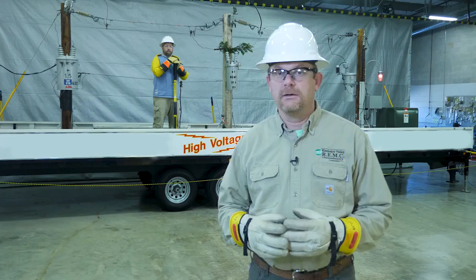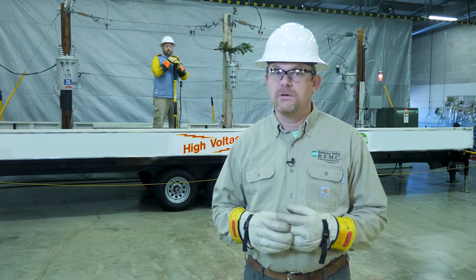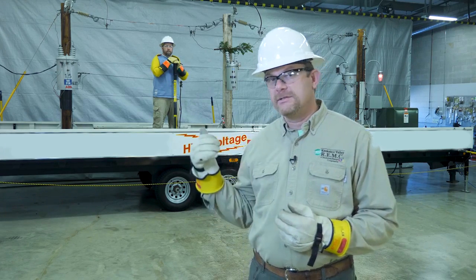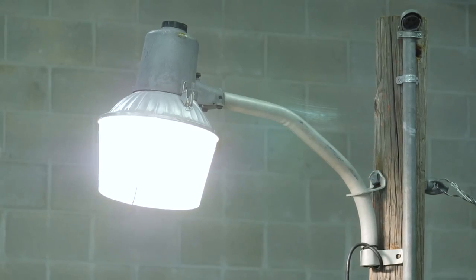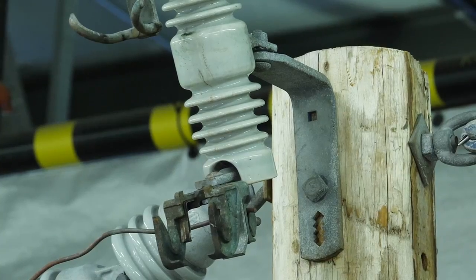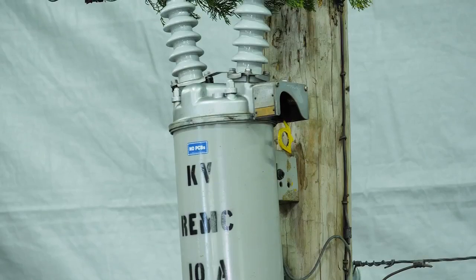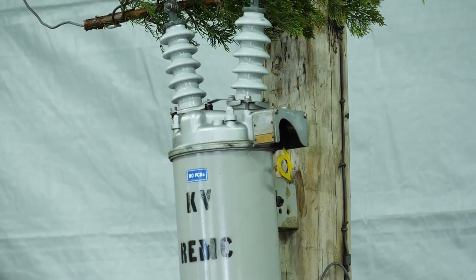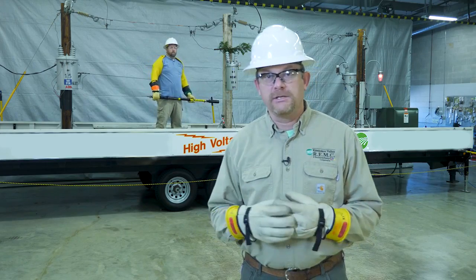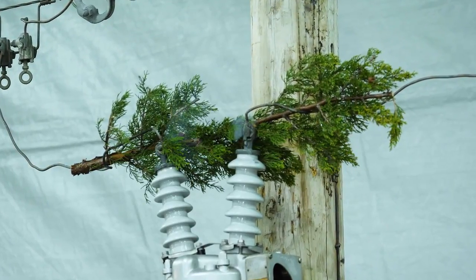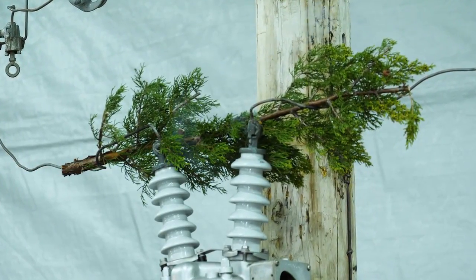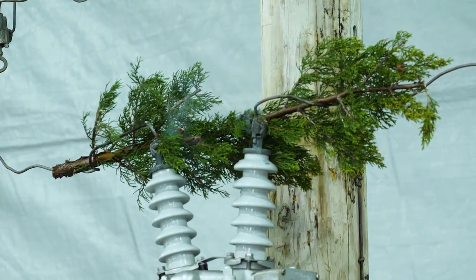Can wood be a conductor? Yes, in the right situation, wood can be a conductor. Now notice the light on the pole is lit, and also notice there's no fuse in the center cutout, and the handle on the side of the recloser is down. Now how is that possible? Well, there's a tree branch across the 2 wires on top of the recloser. This tree branch is conducting the electricity that is energizing the light.